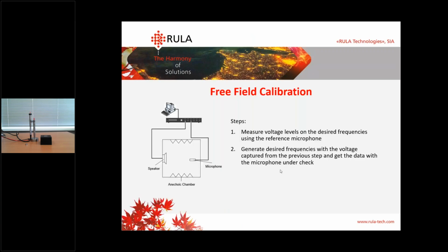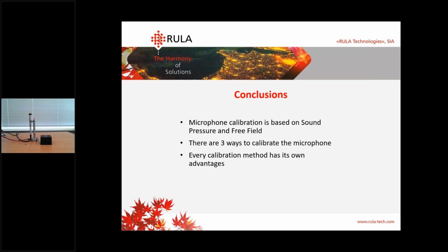Let's go back to the presentation. And so today I told you some information about the microphone calibration module, told you that all the calibration ways are based on two principles, sound pressure and free field. We discussed all three ways to calibrate the measuring microphone and discussed the advantages of each method. Now I would like to ask several questions to Felix, and maybe while I will be asking them, you will also have a desire to ask something about microphone calibration. So the first question is, what standards do we follow? Using the microphone calibration, we follow IEC 61094. It's the basic microphone calibration and verification standard.